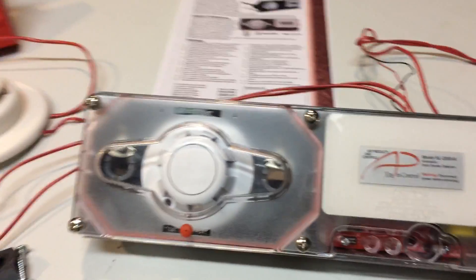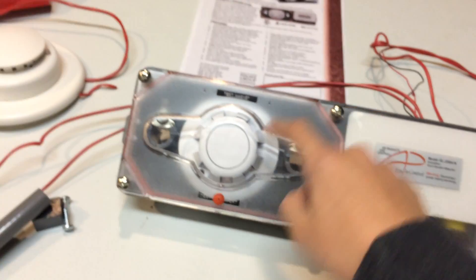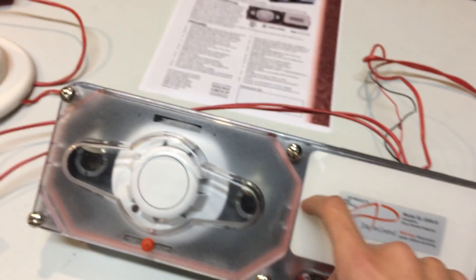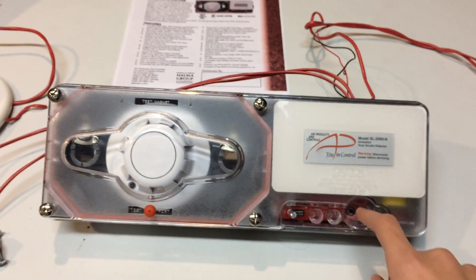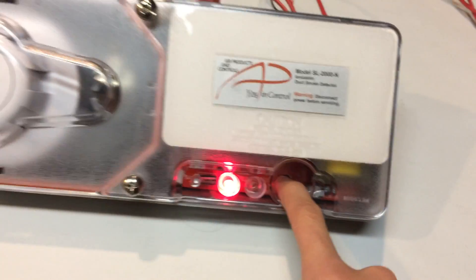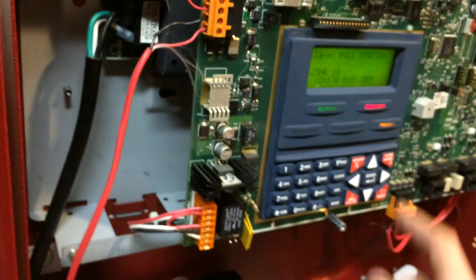Now I'm going to demonstrate doing a manual test from the duct detector. Suppose there isn't a key switch, but you still need to test the duct detector. Right in there is a little button, and it basically trips it. What will happen is I will test it — it will go into alarm. The second I release the button, this will stop going into alarm because the duct detector doesn't think there's an emergency anymore. But since it's already tripped the panel, the panel will stay on and in alarm. The panel just went into alarm. See, once I release it, the piezo stops. And the panel went into alarm.